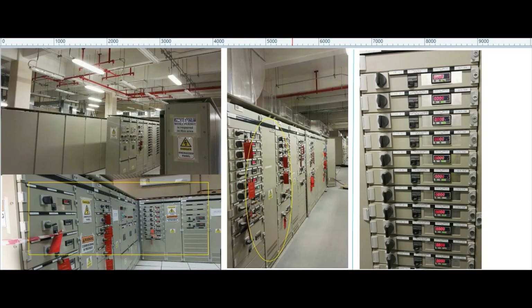In this snap you can see these are the vertical LV modules. These are very small LV modules. Suppose 15 kilowatt motor feeder or power feeder, 0.55, 0.75 kilowatt. In the right hand side also you can see these panels are already charged. In a vertical lineup there are 11 or 12 numbers modules.